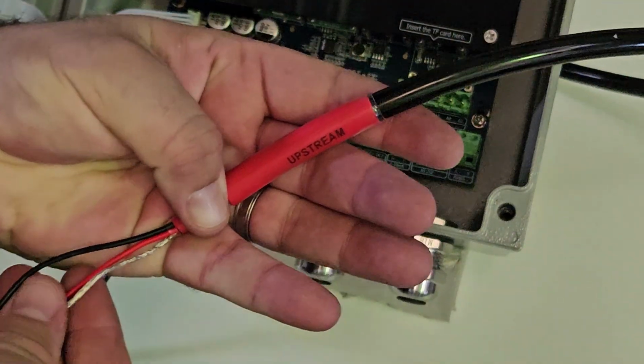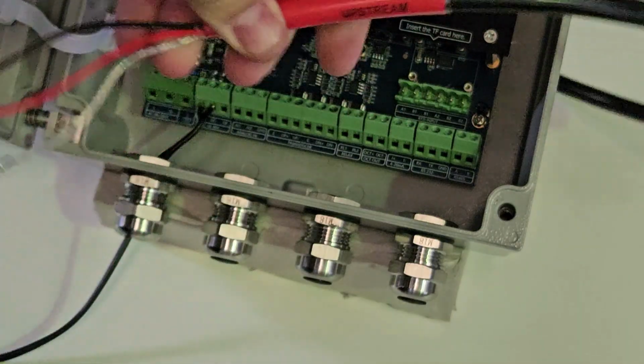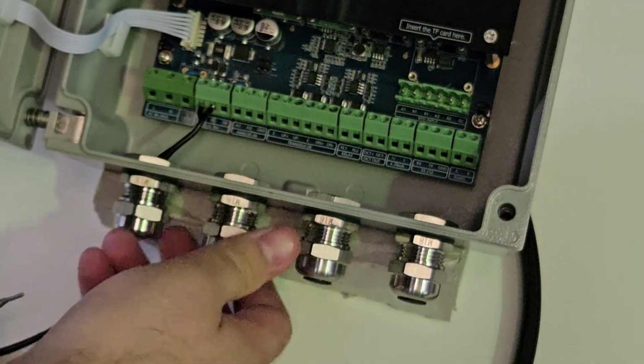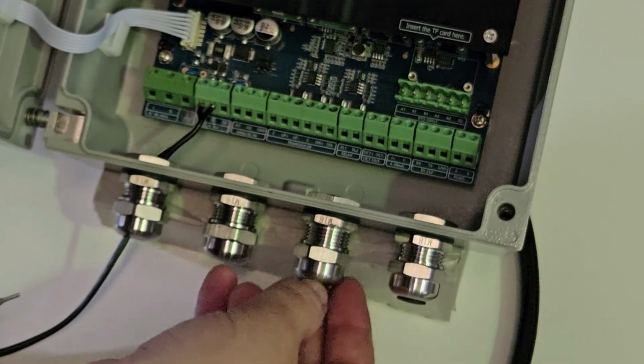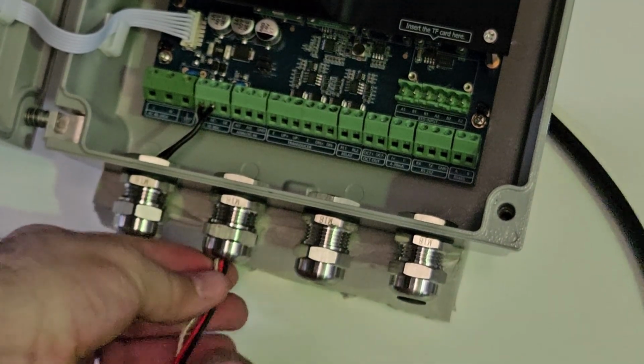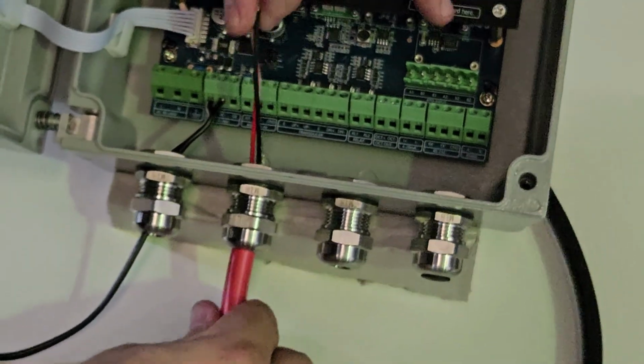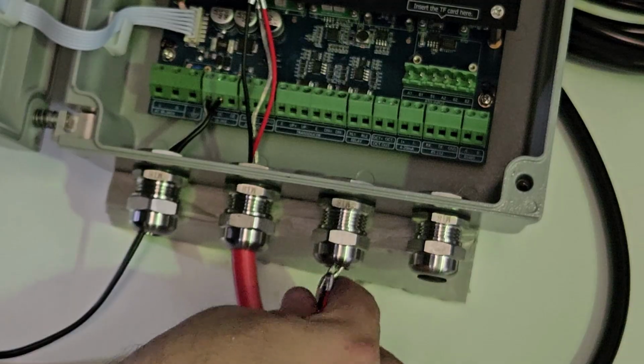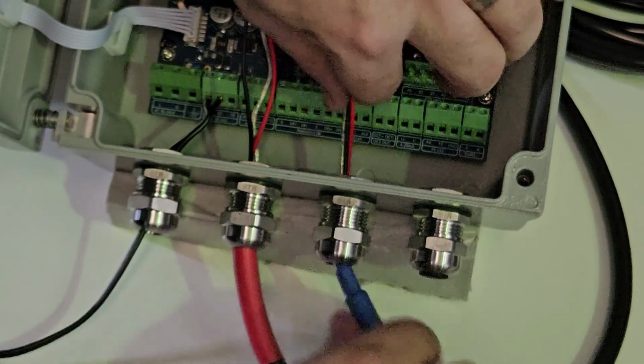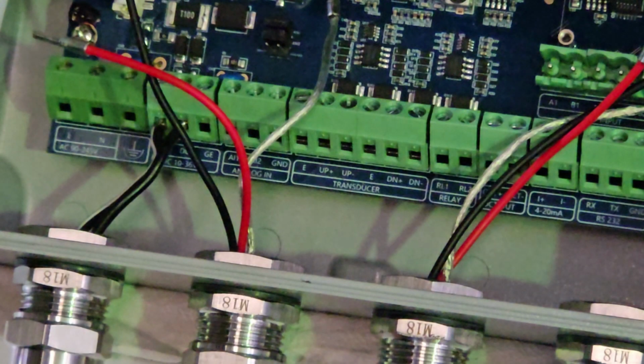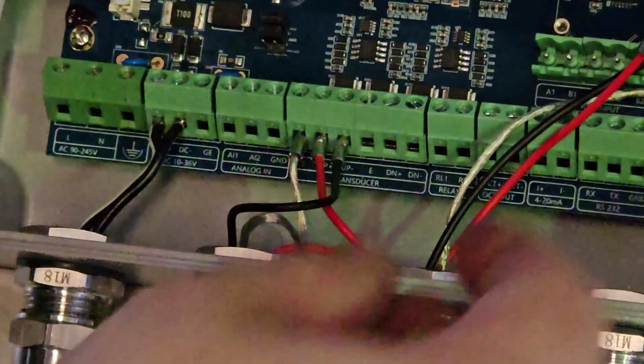Now take the upstream sensor cable and observe that there are 3 wires. Loosen off the glands and remove any plugs blocking entry. Then insert this upstream cable into the second cable gland, as it's best aligned with the upstream cable ports. Then you can take the downstream cable and do the same. Feed it through the cable gland next to it. Insert the wires into each of the ports, noting that the grey wire is for port marked E, red is positive, black is negative. Be sure that the upstream cable is wired to the UP ports and the downstream cable is wired to the DN ports. So we have inserted the wires on the upstream side first, and then inserted the wires to the downstream side.